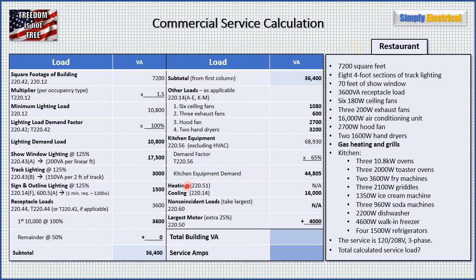Moving on to heating: normally per 220.51 the heating load is at 100%, but we don't have electric heat — we have gas heating. So that's not applicable. For non-coincident loads, per 220.60, we take the largest of any loads that do not operate at the same time. Typically it's heating and cooling that are interlocked so one doesn't run when the other does, and we only take the largest. Since we have no electric heat, it's a moot point, and we just take the 16,000 VA cooling load.